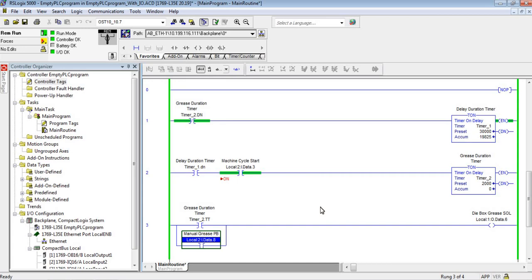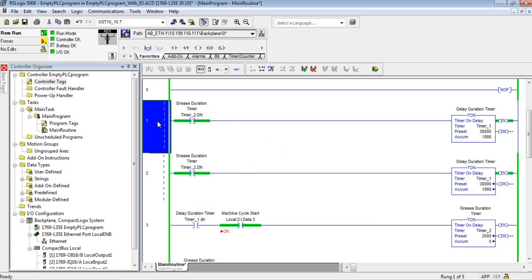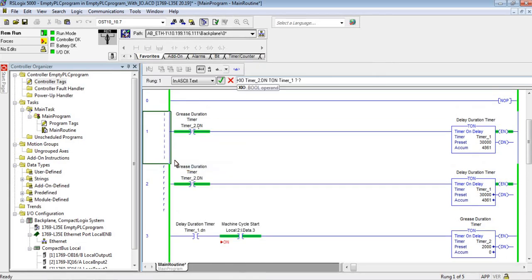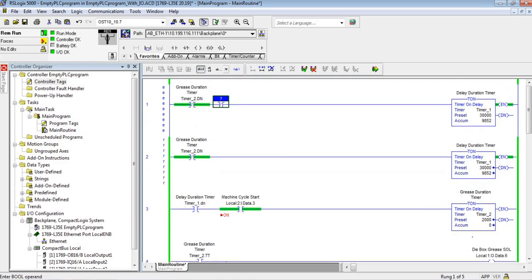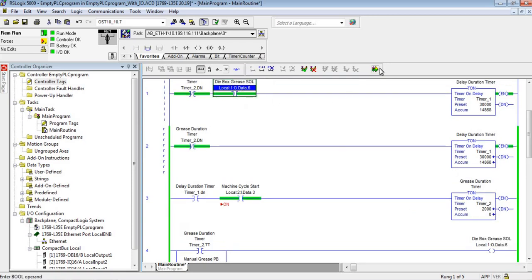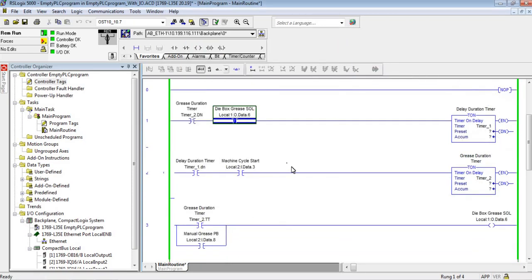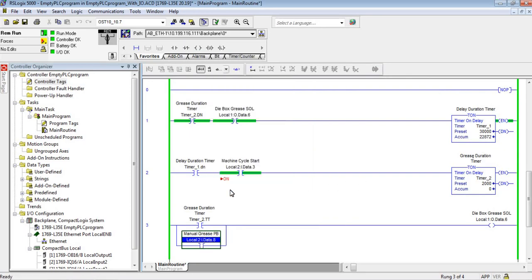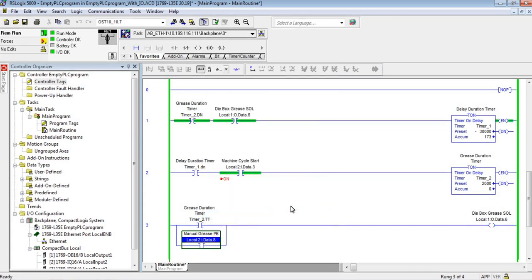The way I would do it - you can reset it with a PLC. You just double-click it, you start editing, or you can right-click and do edit. I would just add a normally closed contact of the die box grease solenoid right here. So now you see the timer is only in 20 seconds, but I'm going to force on this bit and look at that, it zeroed it out because it died, it can't get power anymore. So now when I let go, it starts once again.